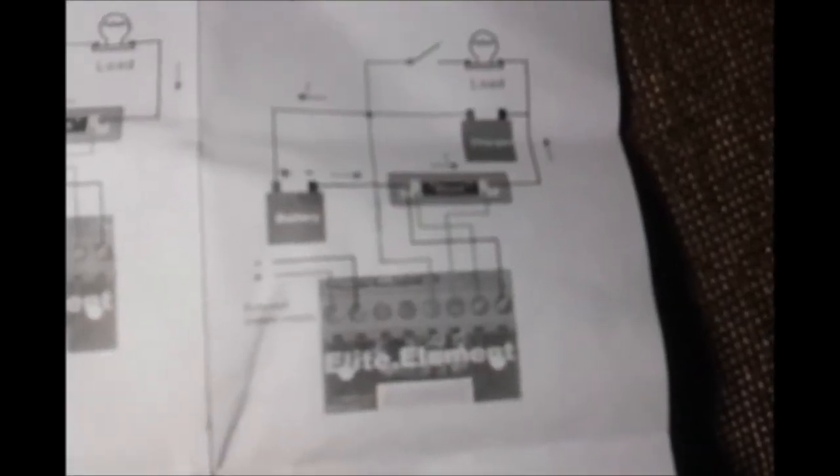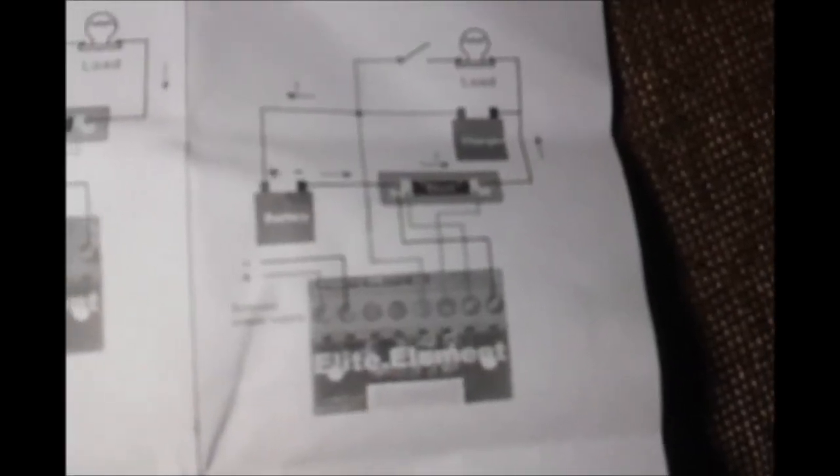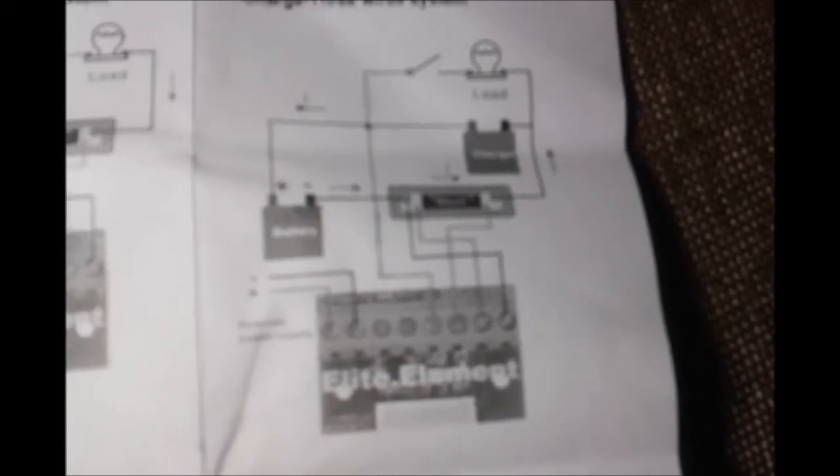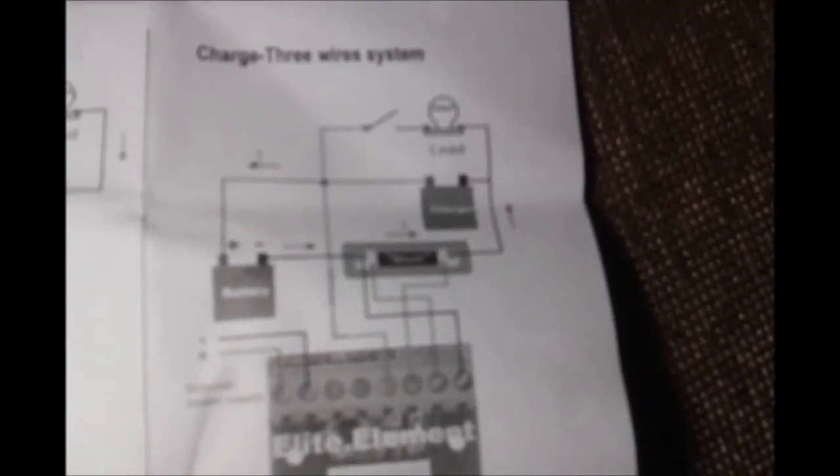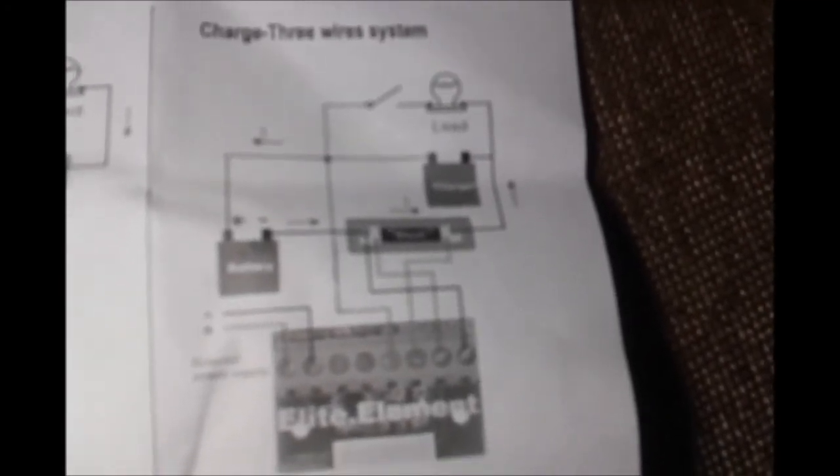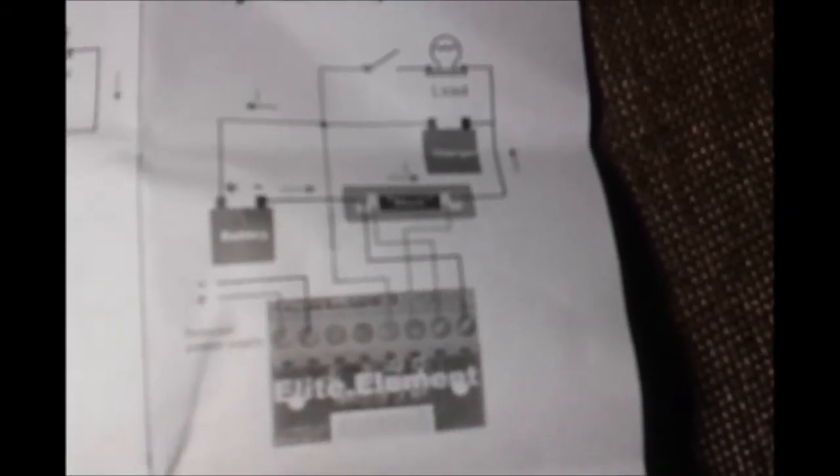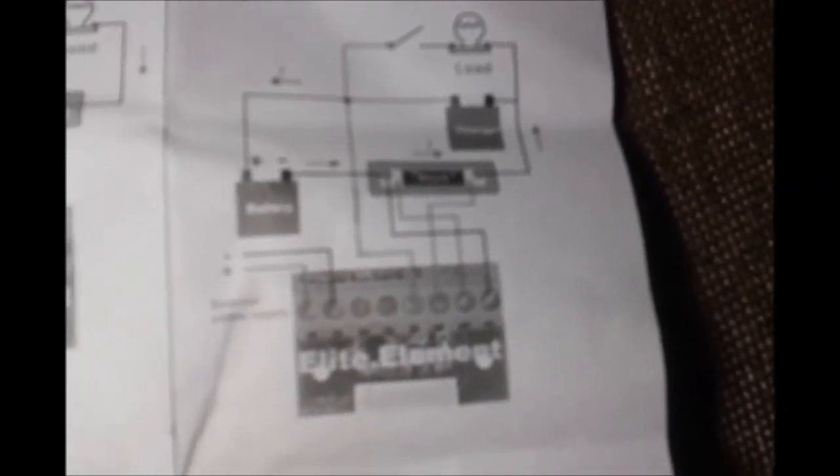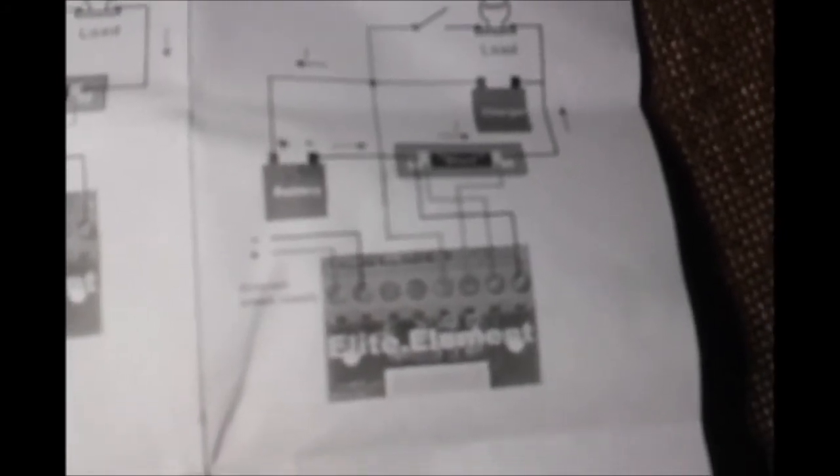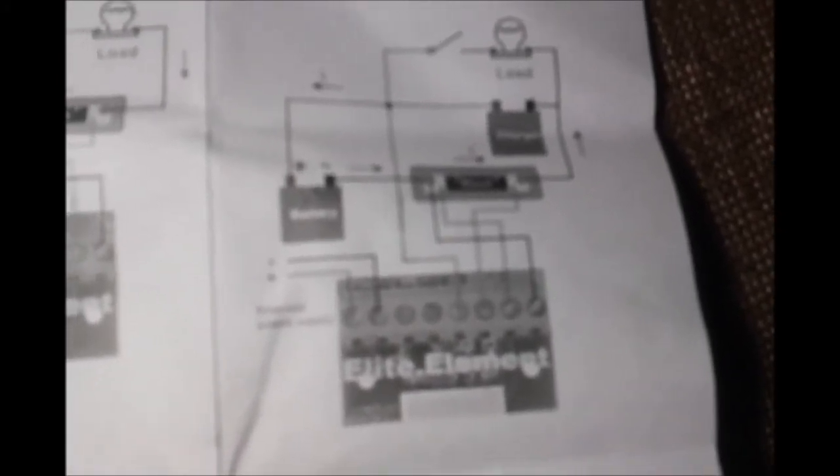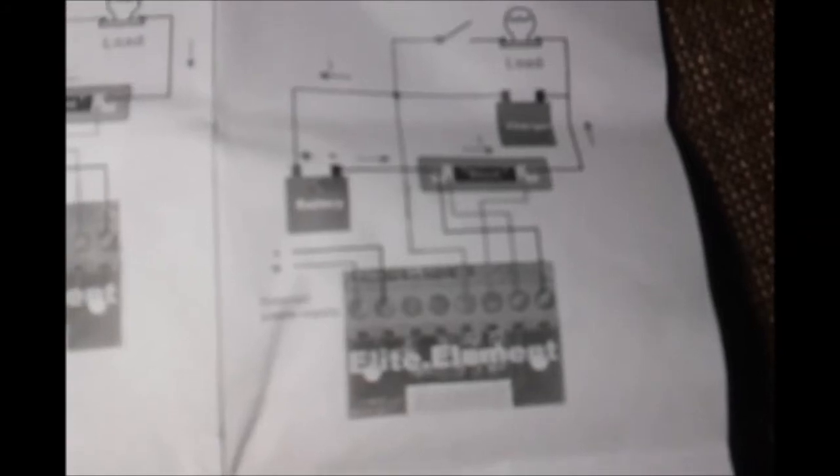Examining the wiring diagram that comes with the meter, we can see that the shunt goes between the battery's negative and the charger's negative and load negative. The charger and load are on one side of the shunt, the battery is on the other. It is important that you can then monitor any current flowing from the charger to the battery or from the battery back to the load.